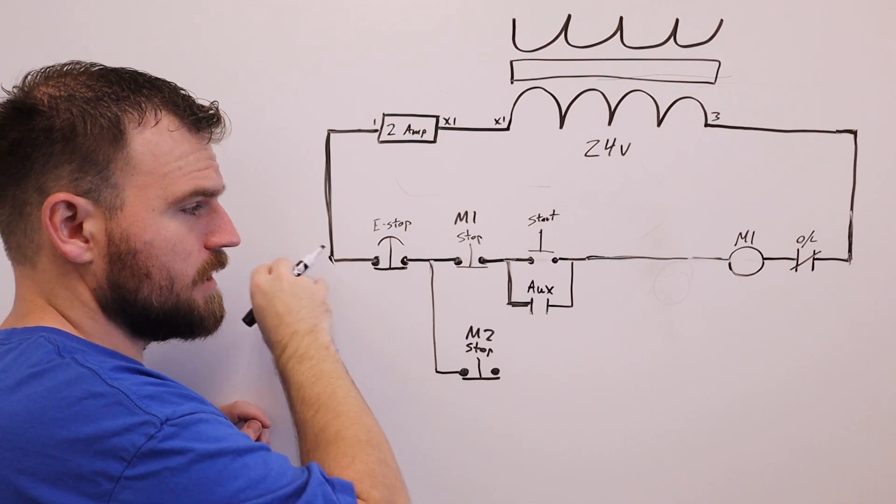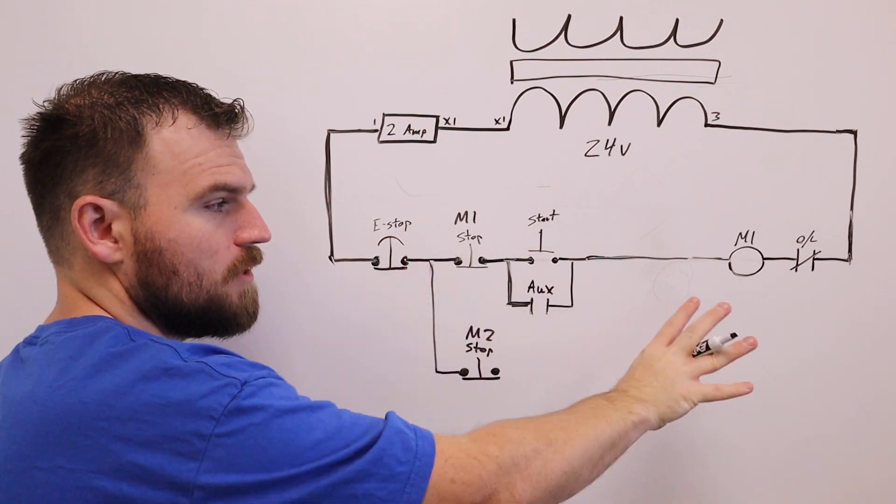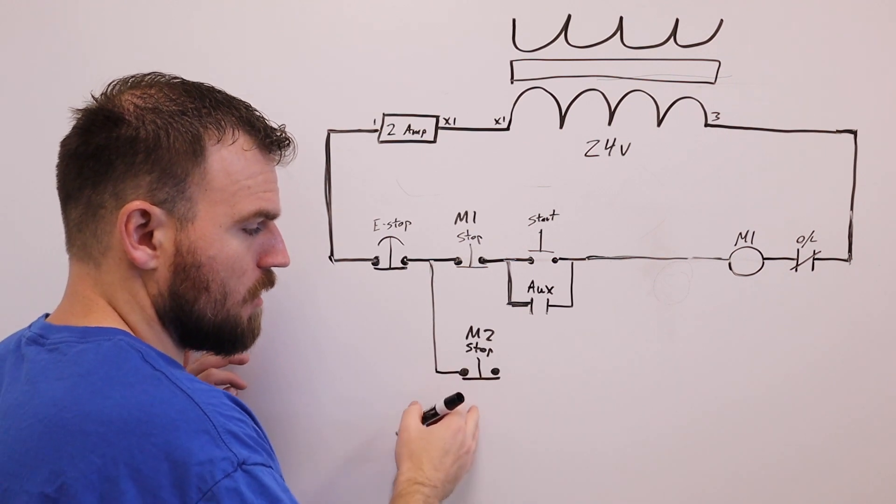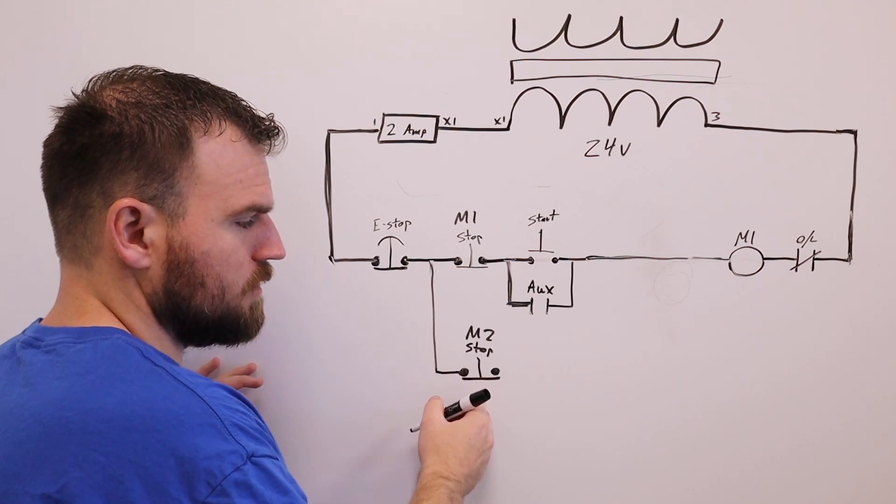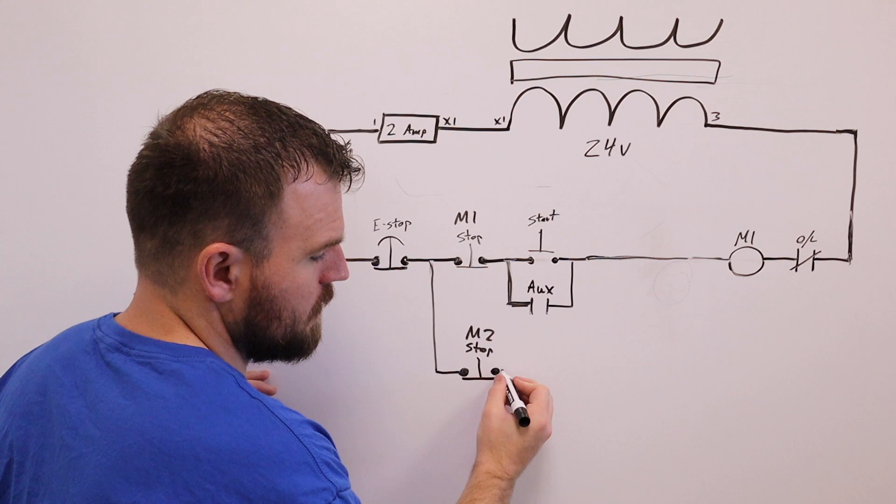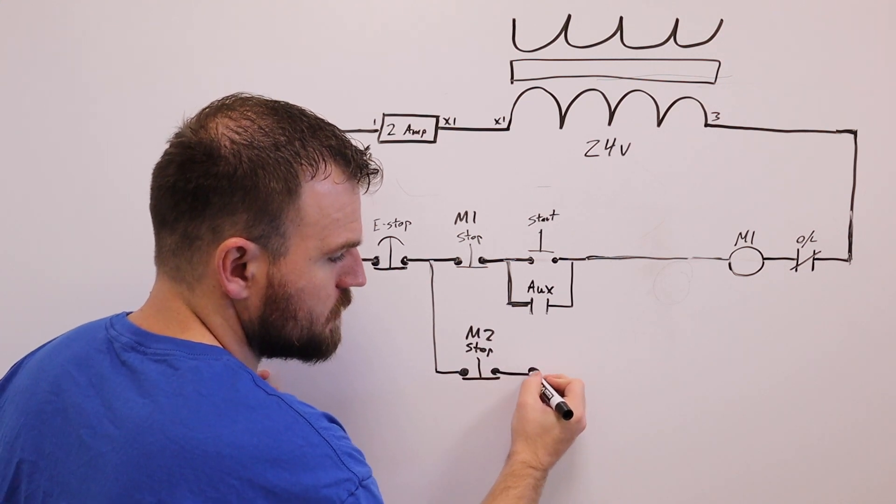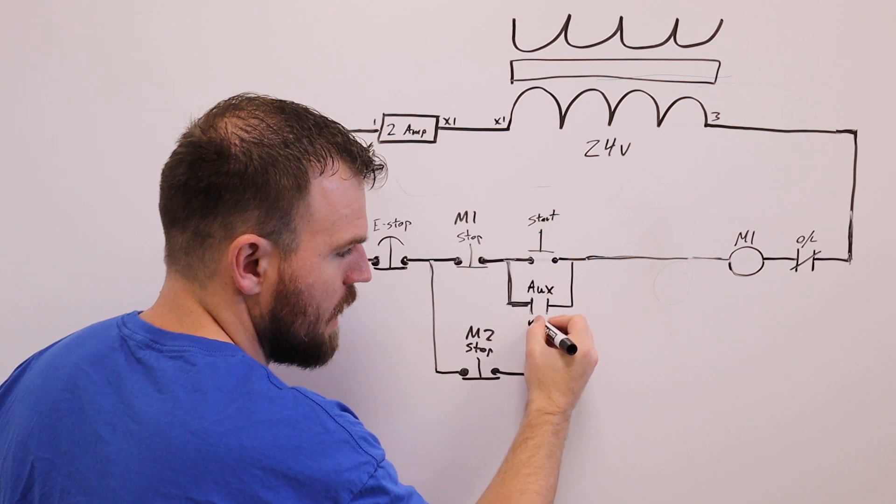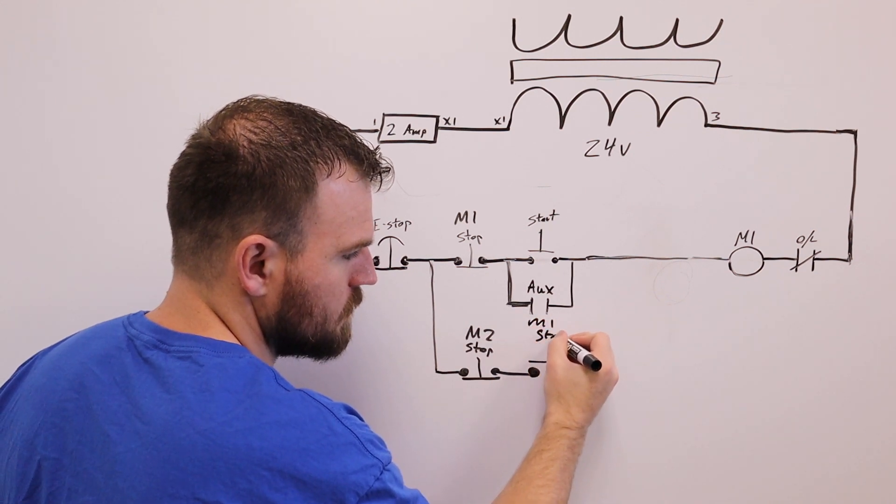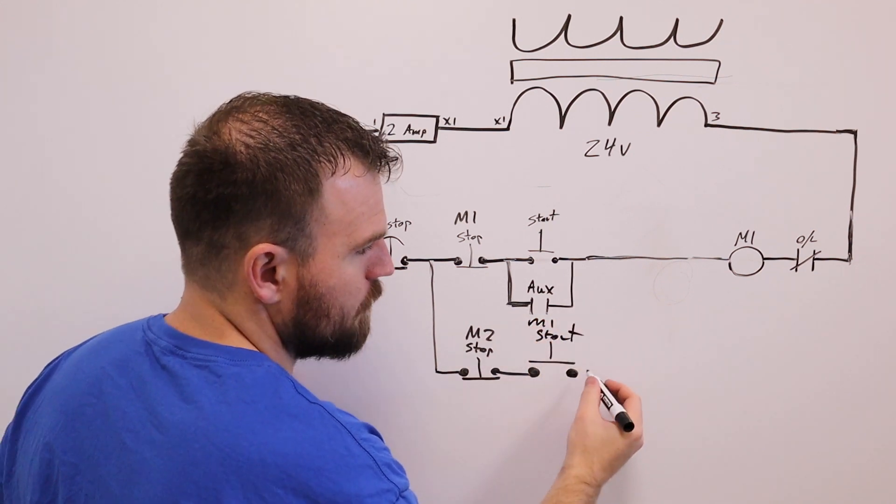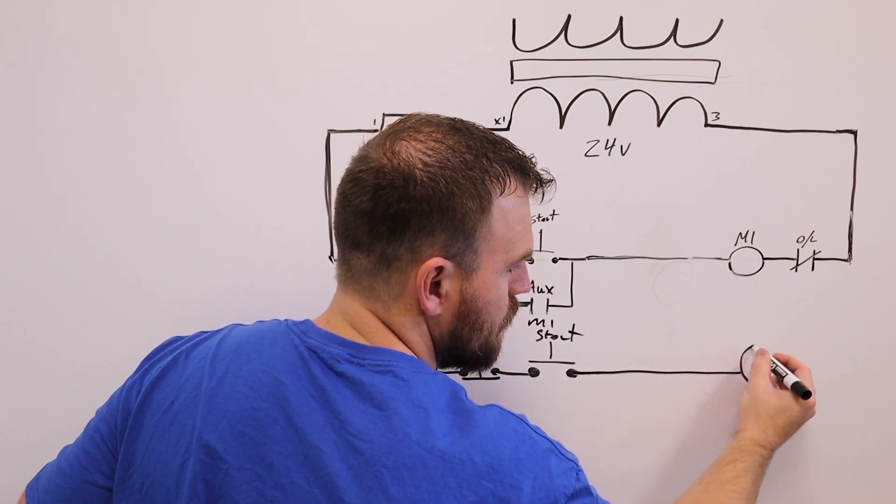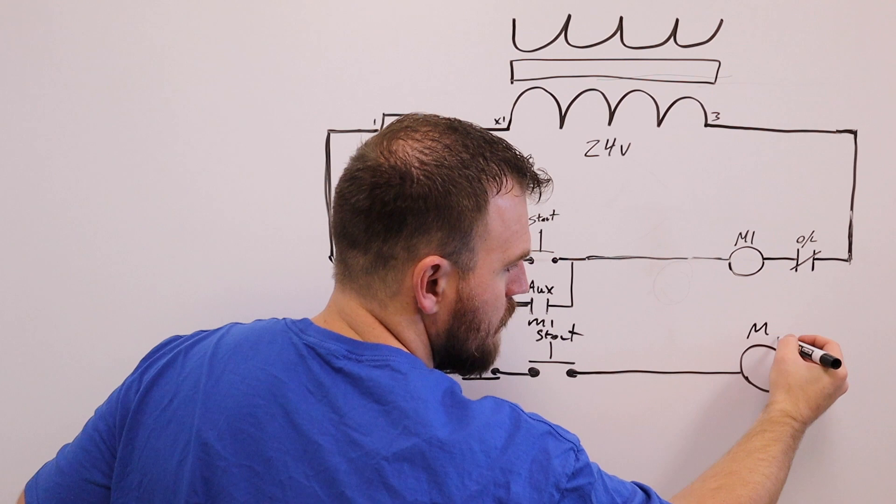Like I said, if we press this e-stop, it's going to kill the circuit for both of these motor controls that we're building. The next thing we're going to do in our M2 run is come in with our start switch, just like so. We'll just put M1 start, and then we're going to go over into another motor coil, and this one we'll put M2 on.